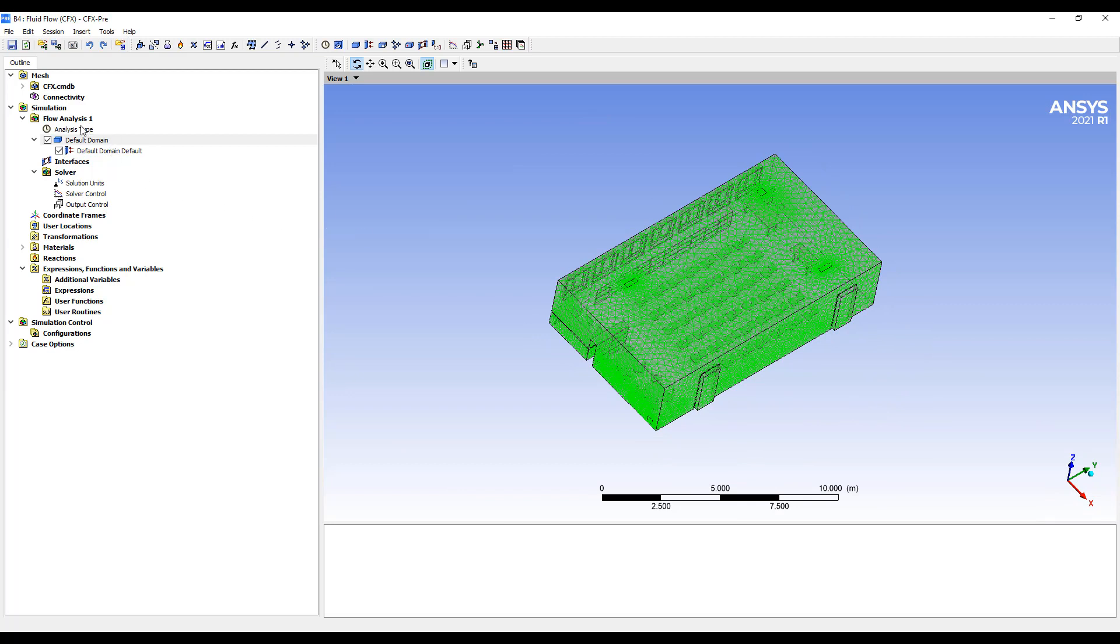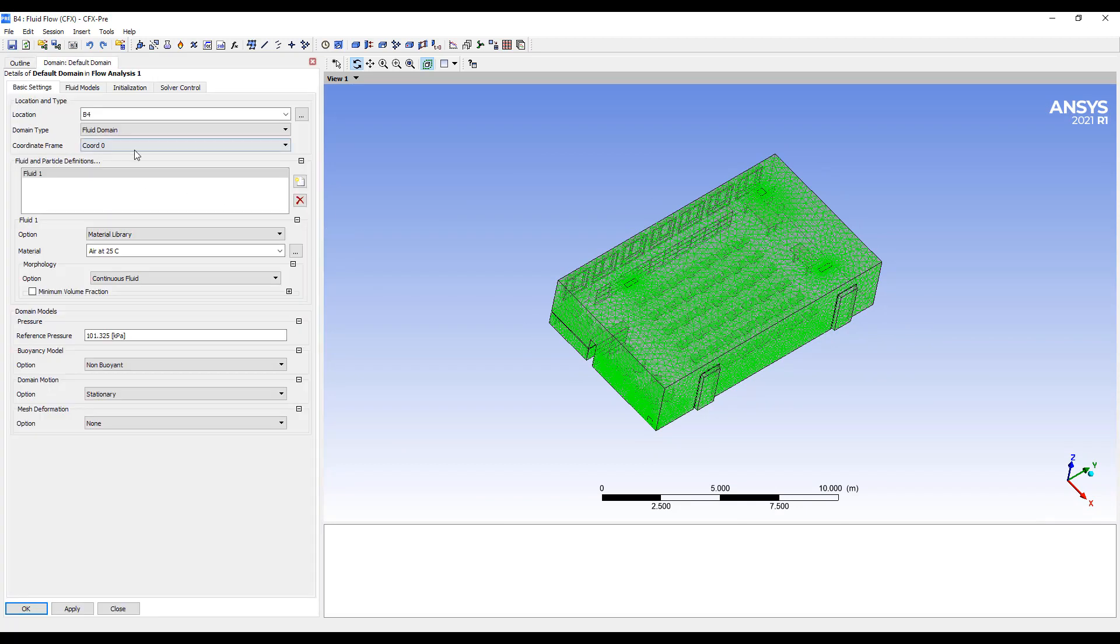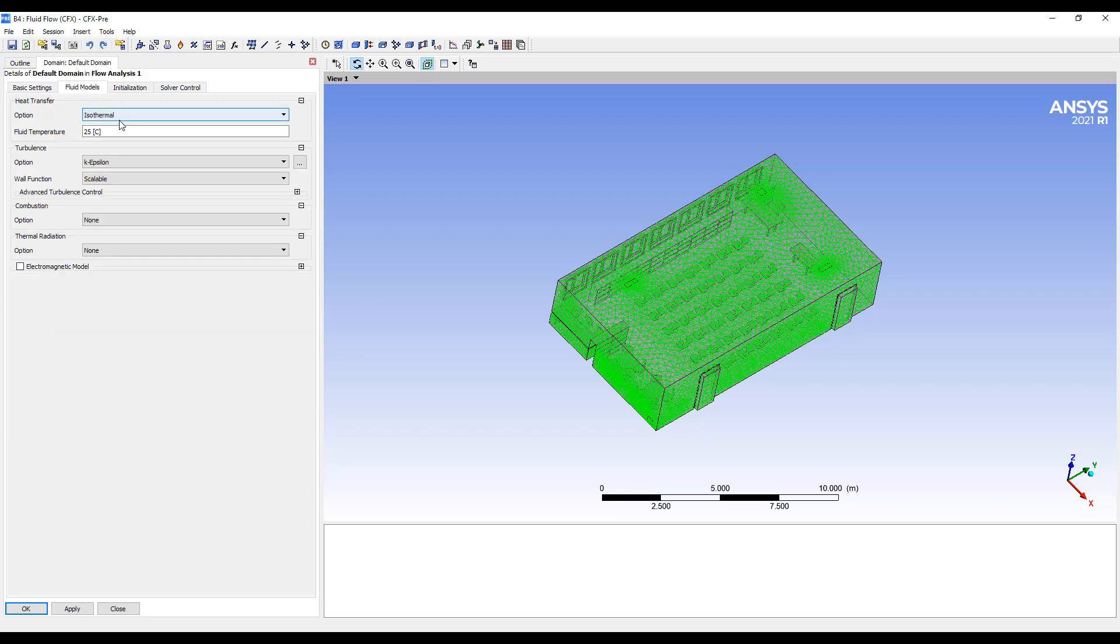This is the CFD simulation environment. We're going to use air at 25 degrees. In this case, we're just going to do a flow analysis, not including buoyancy. I'll do that next. Fluid model, isothermal, k-epsilon turbulence model.